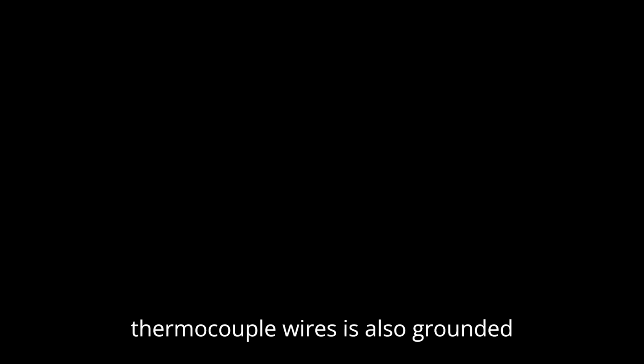A grounding loop can occur if the tip of the thermocouple, the hot junction, is electrically bonded to the metal pipe or vessel it's measuring. This is called a grounded junction thermocouple, often chosen for faster response. Okay. If that pipe or vessel is grounded somewhere and the measuring instrument or transmitter connected to the other end of the thermocouple wires is also grounded somewhere else in the plant's electrical system, you can create an unwanted secondary electrical circuit or loop through the ground connections.